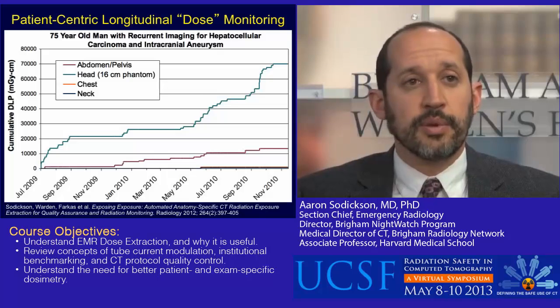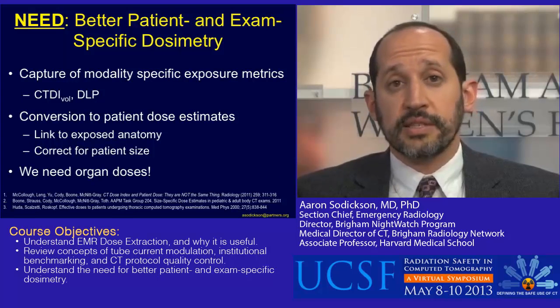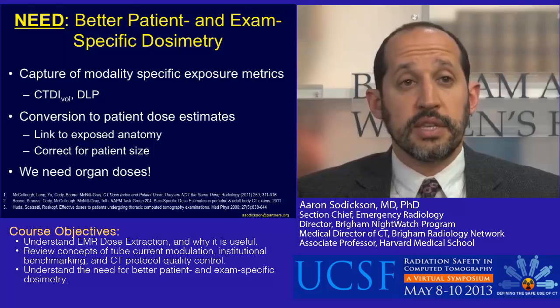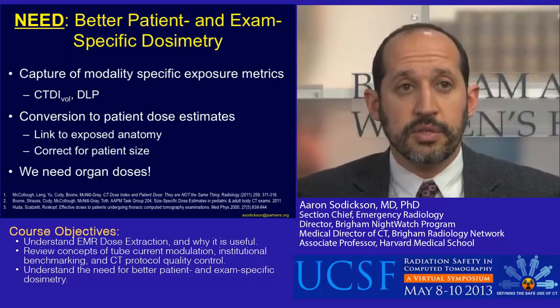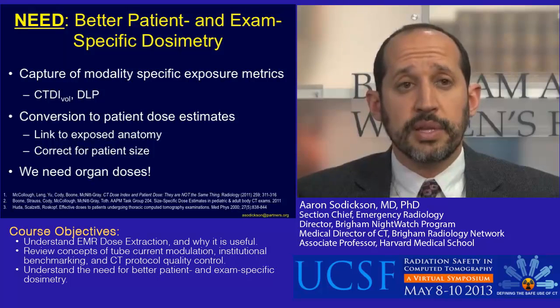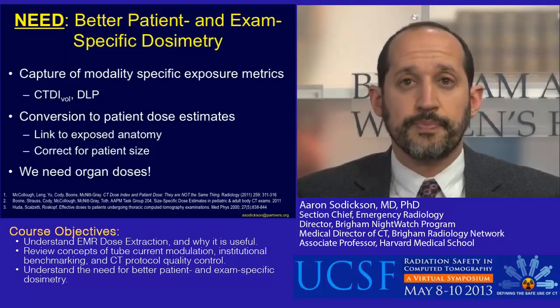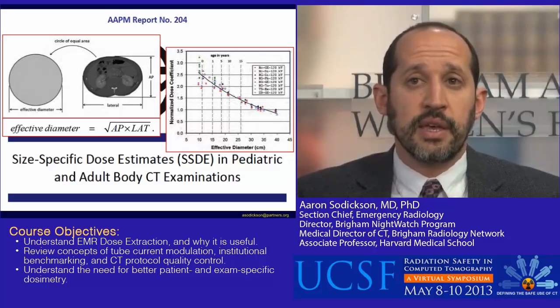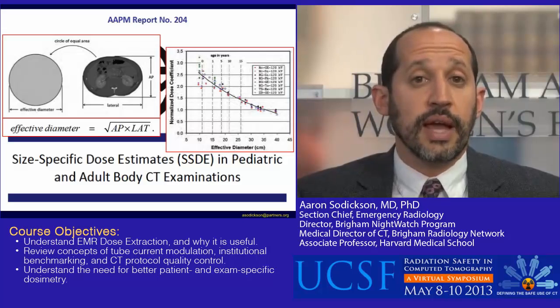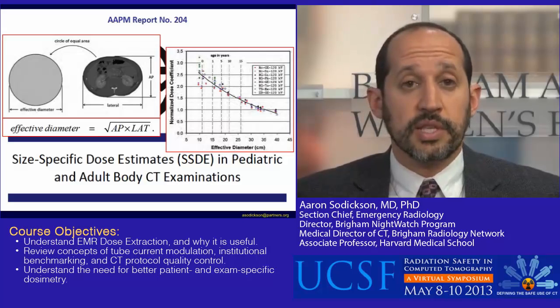Wouldn't it be nice to actually see what a patient's actual doses were doing over time? In order to do this, we need not only to capture the CTDI and DLP, but to convert it to a meaningful patient dose estimate. To do that, we need to know what anatomy was exposed, and we need to correct for patient size — because ultimately many of us feel we need to get to organ dose if we're going to think about anything patient-centric around radiation exposure. The AAPM in this report made great strides towards doing this by defining an effective diameter that can simply be measured off CT scans, using this to create normalized dose coefficients or correction values that can be multiplied by the CTDI to get a number that more closely approximates the organ doses one would expect to see in a patient.